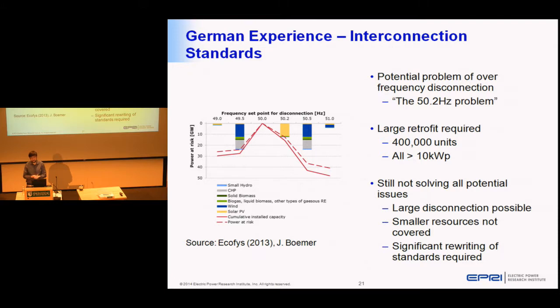Talking to some of the guys in charge of the rollout, they're pretty concerned that the electricians doing it don't even really know why they're doing it—they're just told to turn something on an inverter. They've gone back out and tested, and found that something like 3 in 10 doesn't actually make the changes properly. So they still don't know if and when something large happens on the system whether they'll lose a lot of this PV. It's still going to be a big concern.